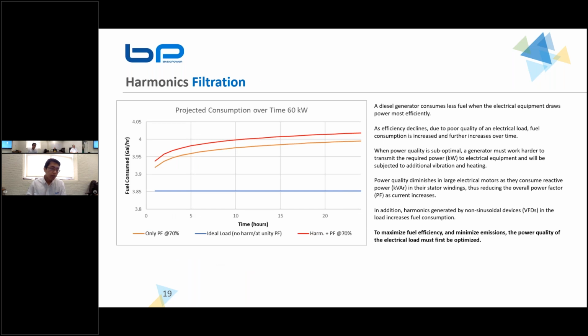And in terms of fuel consumption reduction, this is one of the graphs we were able to produce from our experiment. As you can see, the blue line represents an ideal load. What we have is a load center where we can decide how optimized that load is. It's a custom load center where we can choose what the harmonics are and what the power factors are. And we put it on a generator. We noticed that as we ran it throughout the hours, it remained pretty constant when we had an ideal load. The moment we put on a power factor of 70%, meaning it's pretty much 70% efficient instead of 100%, you end up seeing that the curve slowly builds up because of heat, and you'll slowly consume more and more fuel as you run the generator longer and longer. And if you add harmonic distortion on top of that, you'll get an even larger consumption increase.